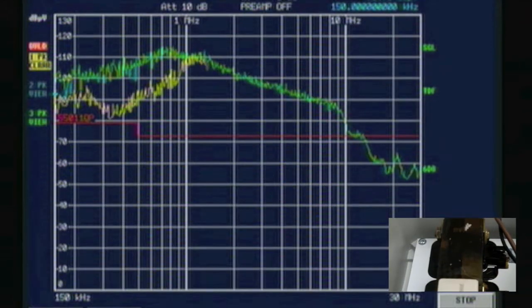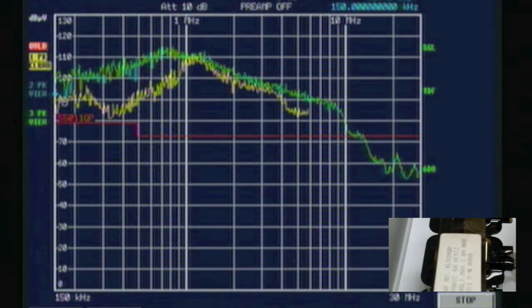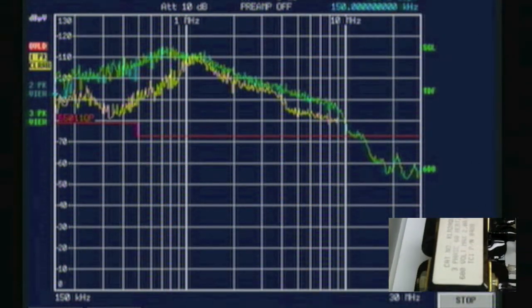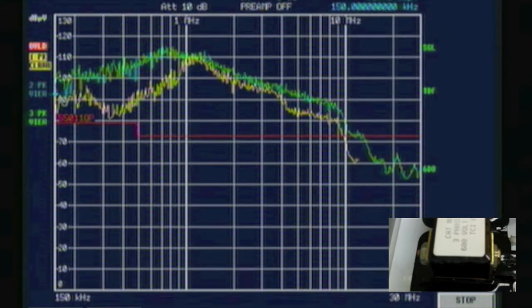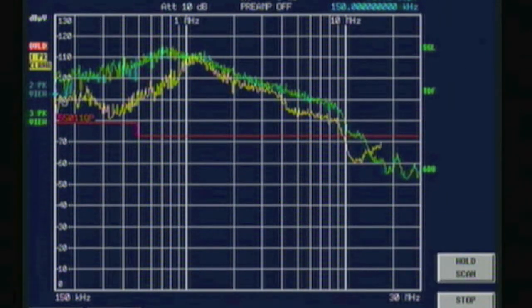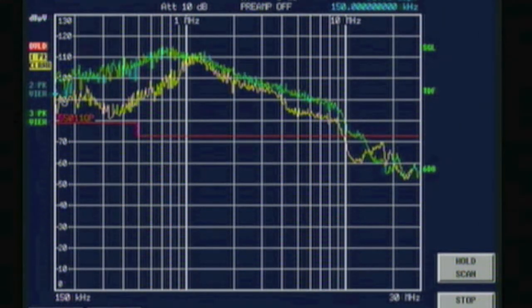This graph line in yellow shows the electrical noise generated by the AC drive with a line reactor installed in series with the drive. The effect of the line reactor is visible only in the low frequency range of 150 kHz to 800 kHz.